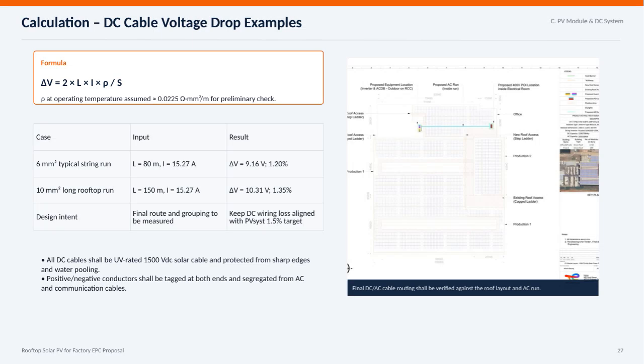Here we have the calculation for DC cable voltage drop in our rooftop solar PV system. The formula we use is delta V equals 2 times the cable length times current, times resistivity, divided by the conductor cross-sectional area. For our preliminary check, we assume the resistivity at operating temperature to be approximately 0.0225 ohm millimeters squared per meter. Looking at the examples, for a typical 6 millimeters squared string run of 80 meters carrying 15.27 amps, the voltage drop is 9.16 volts, which is about 1.2%.